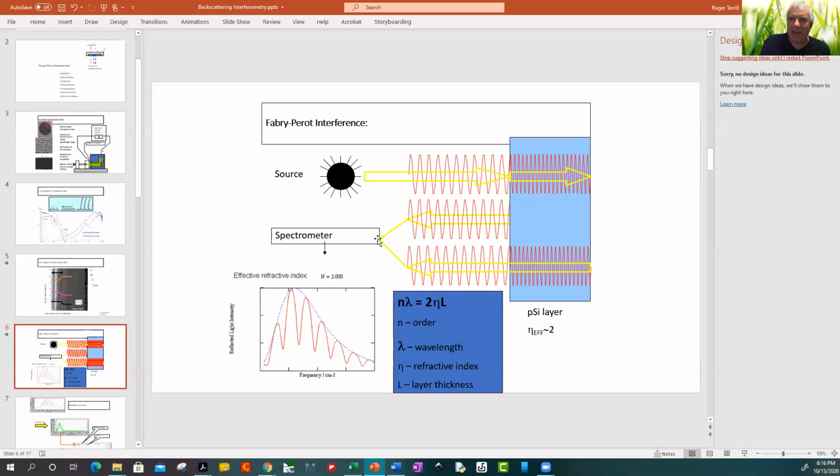So the light comes into the spectrometer and it bounces off a couple of mirrors, and then it bounces off a grating, and then it's all separated by wavelength. And the rainbow shines on an array detector, and each pixel in the array is represented here in this frequency spectrum. So the spectrometer has both the wavelength separation and the detector all in one. And it's an array detector, so it sees everything all the time.